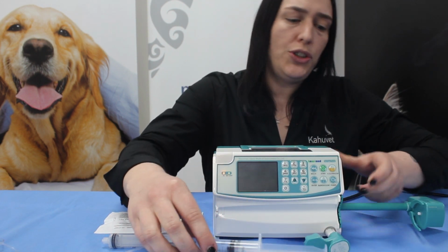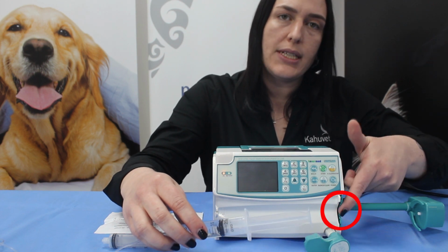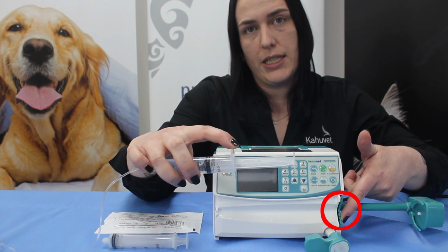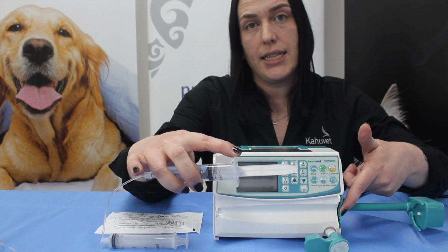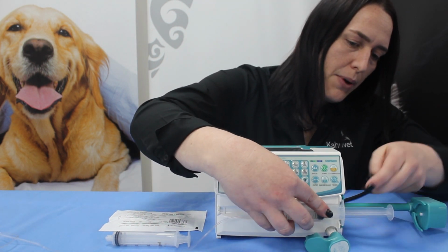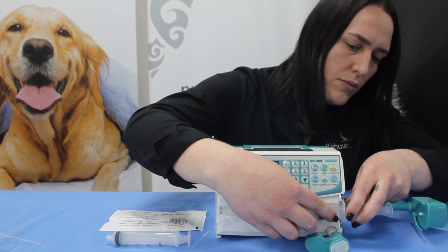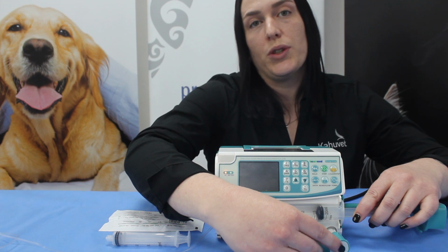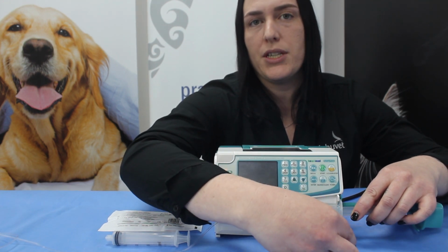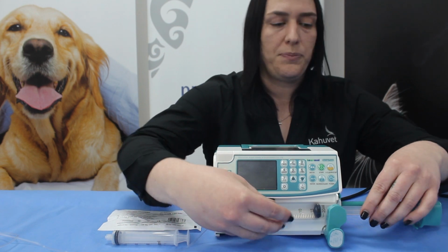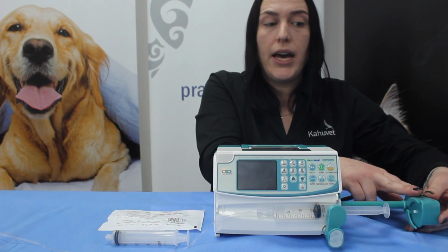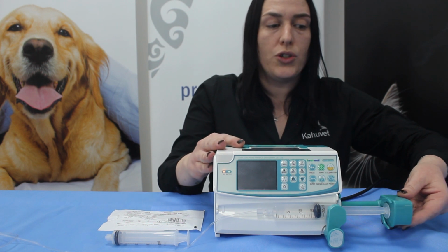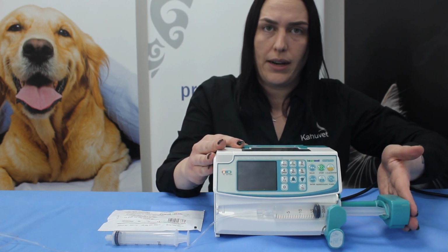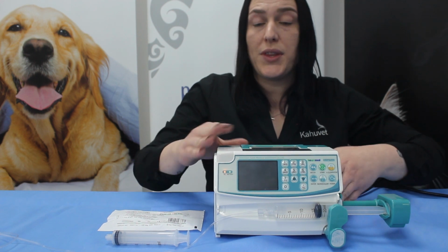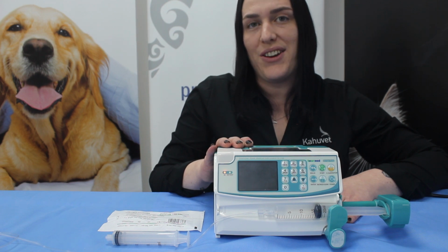We can then take our syringe and we can see these grooves at the side here is where we're going to be popping this part of the syringe into and making sure it's nicely aligned. So we can just go ahead and pop that in position. We can then use our syringe holding clamp if we rotate that back into position, and it will lock the syringe in place. We can then pop the plunger control down onto the syringe plunger and lock that in place as well. This will then be ready for you to turn on and set your rate and volume to be infused using the display screen and control panel.